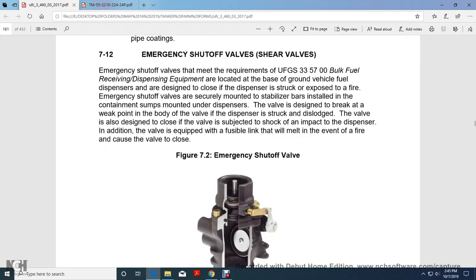Alright, 7.12 Emergency shutoff valves or shear valves. Emergency shutoff valves that meet the requirements of Unified Guidelines Spec 335700, bulk fuel receiving and dispensing equipment, are located on the base ground vehicle fuel dispenser, designed to close if a dispenser is struck or exposed to fire. The emergency shutoff valve is securely mounted with a stabilizer installed in the containment sump mounted under the dispenser.